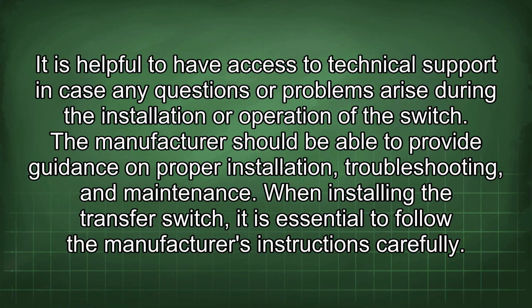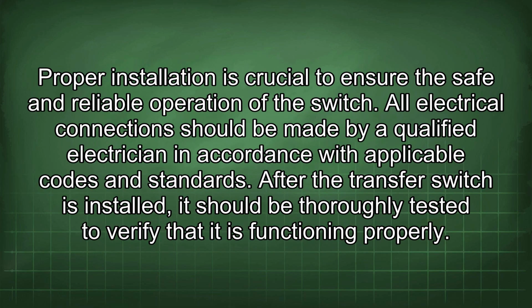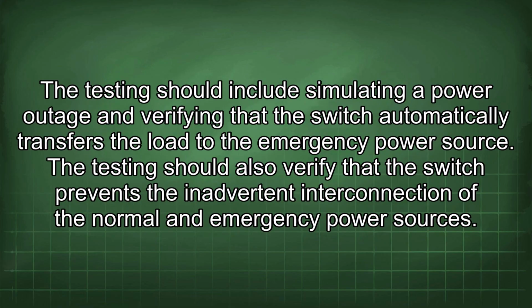When installing the transfer switch, it is essential to follow the manufacturer's instructions carefully. Proper installation is crucial to ensure the safe and reliable operation of the switch. All electrical connections should be made by a qualified electrician in accordance with applicable codes and standards. After the transfer switch is installed, it should be thoroughly tested to verify that it is functioning properly. The testing should include simulating a power outage and verifying that the switch automatically transfers the load to the emergency power source. The testing should also verify that the switch prevents the inadvertent interconnection of the normal and emergency power sources.